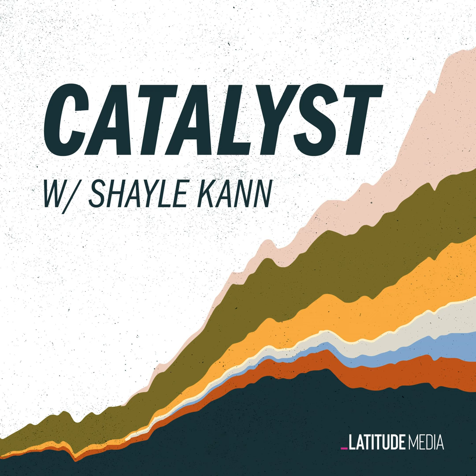Probably one of the few places in the world where that is becoming the norm is Dublin. But the reason that's the norm in Dublin is the grid operator was moving towards a moratorium on data centers because Dublin has one of the highest concentrations of data centers in the world. It's almost 20% of the entire country of Ireland's electricity that goes to data centers, and they're almost all in Dublin. So the grid operator was going to establish a moratorium. And we were actually able to go convince them that what you should actually do is require data centers to be dispatchable in exchange for a grid connection. So now every new data center in Dublin is getting a natural gas generator behind the meter so it can be flexible and avoid that contribution to system peak. So those behind-the-meter opportunities are enormous, and they're certainly known, but I think they're largely untapped and underutilized.